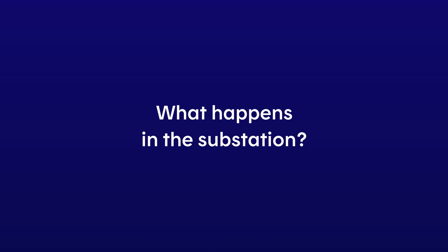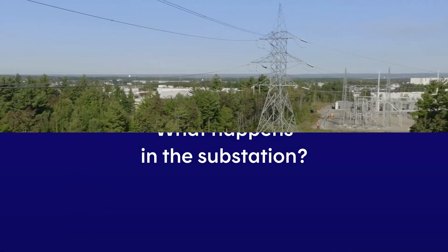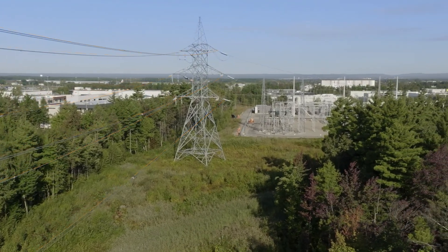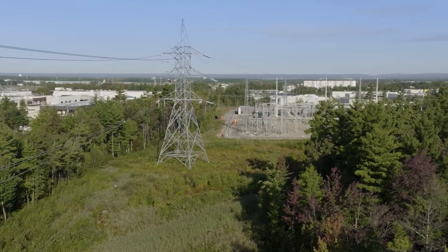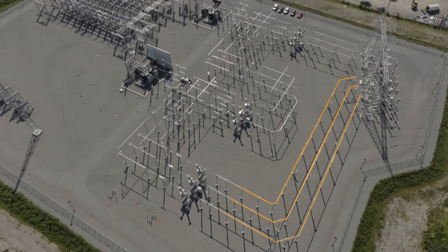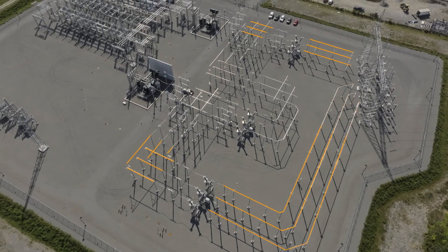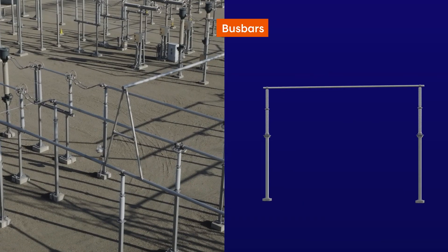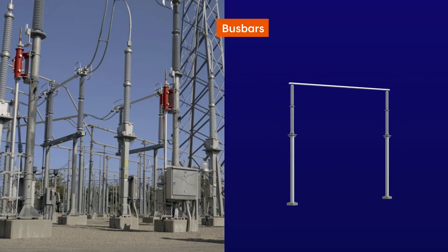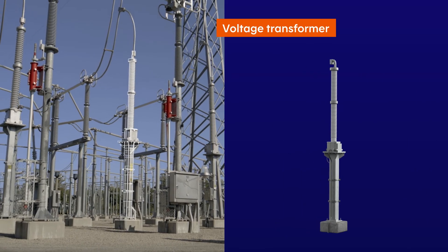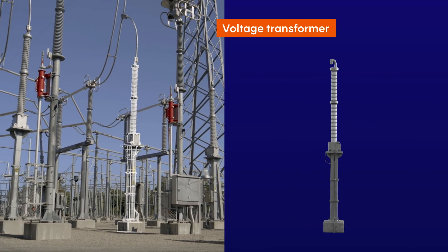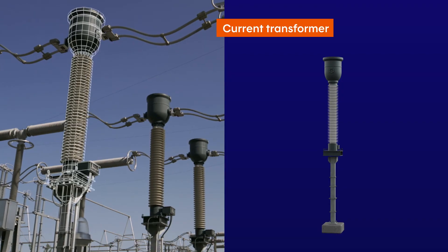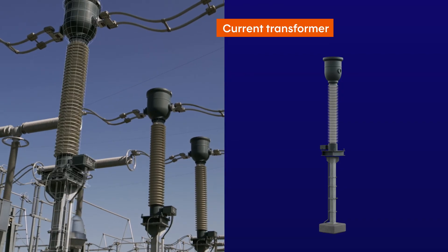But what happens in a substation? Electricity enters through flexible conductors, which are cables supported by towers. In the substation, it passes through bus bars, which are usually large, rigid conductors. A voltage transformer measures the voltage, and a current transformer measures the intensity of the current in amperes.